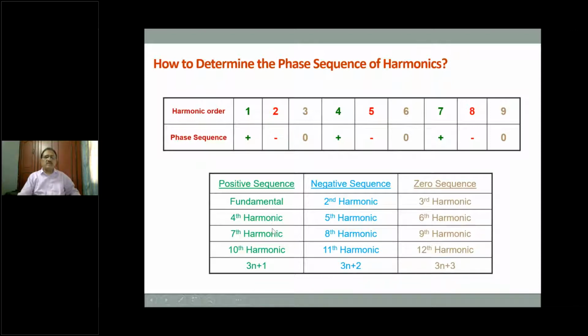Now, about negative sequence and positive sequence: a 6 pulse drive in a 3-phase VFD will cause 5th and 7th order harmonics. It is a 6 pulse drive, but the harmonics will be caused, like I told you, as odd numbers, not even numbers. So 5th and 7th will be shown. 5th is negative sequence, 7th is positive sequence. So you will add 5 plus 6, 11, 11 plus 6, 17, 17 plus 6, 23, 23 plus 6, 29. These are called negative sequence harmonics.